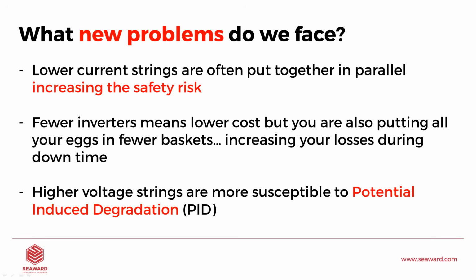And the good thing about our instrument, the Solar Utility Pro, is that because we're testing for open circuit voltage and comparing our measured value to our expected value, we can really tell if a system is being affected by PID just from that reading alone. Sometimes a curve trace is really unnecessary in that regard.